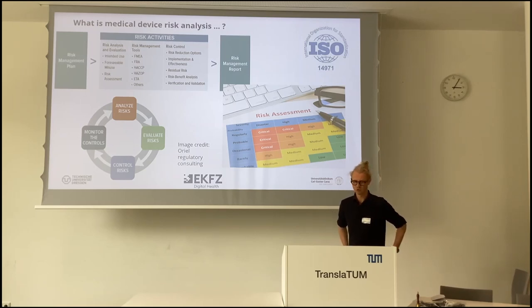The model you might theoretically be using slightly falls to the wayside, it's very pragmatic. You then develop and design risk control measures for your device. You put a quantification on this in terms of the occurrence rate of a risk and its severity, then predict from your control or mitigation measures the extent to which you reduce risk.